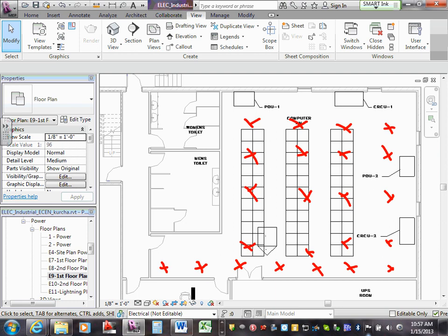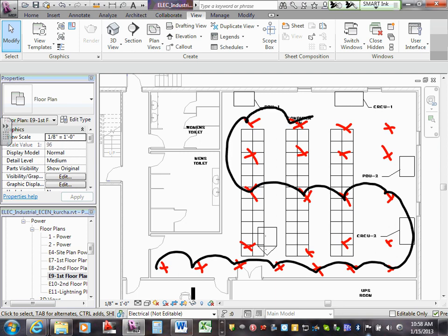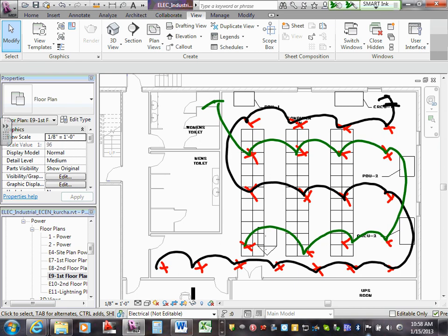So when we're talking about cross zoning, you got all your smoke detectors in the area 9 feet on center. When you're cross zoning them, the circuits are going to look like this. Next one. That's going back to your panel. And the way it is, if any one of these smoke detectors goes off, it's not going to do anything. It has to take both. You have to have it on 2 different lines. As soon as those go off, then the pre-action system will release, water will flow into the system, system charge will start, the heads go off, and we'll turn off that EPO system.